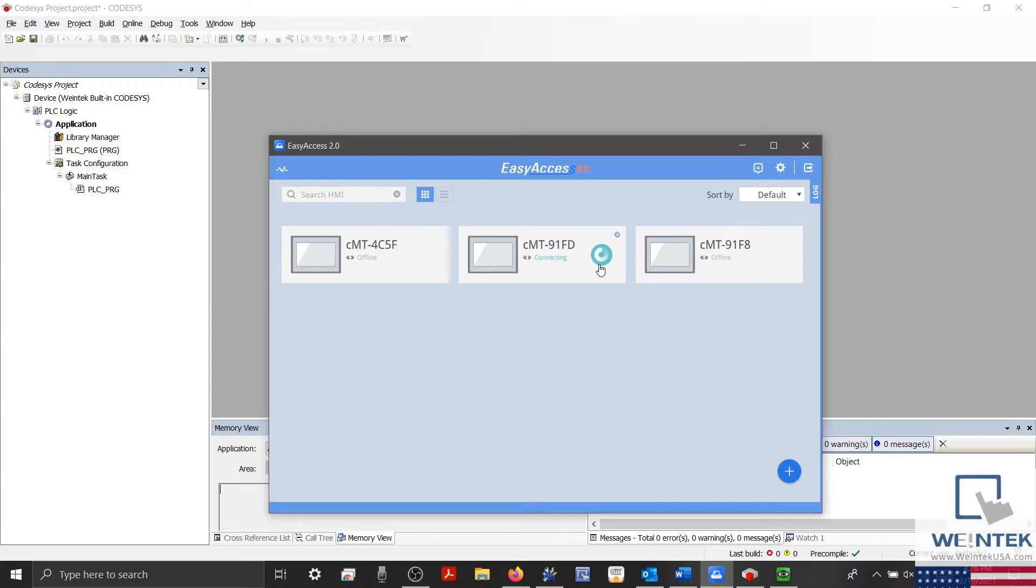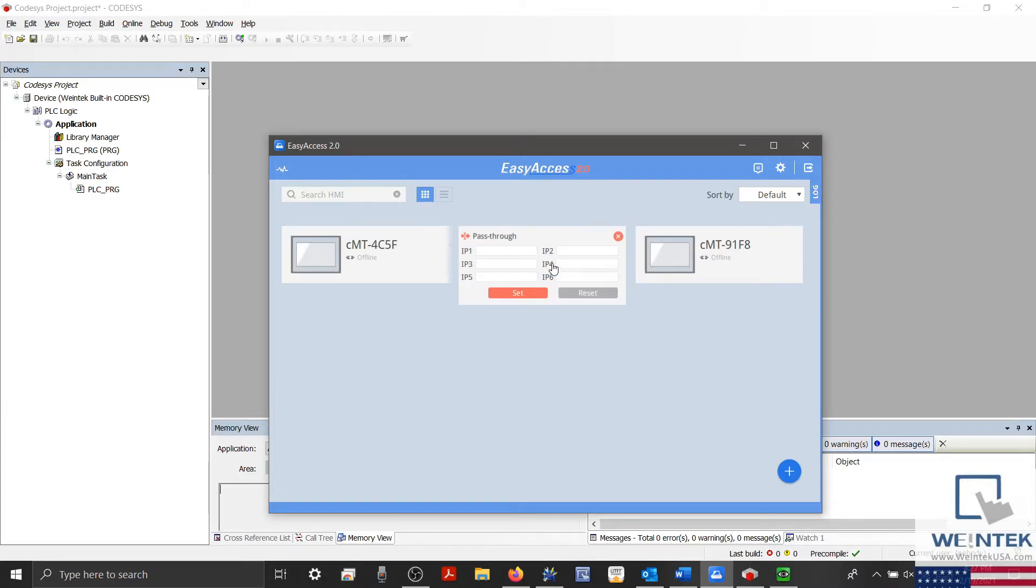Once connected, we'll select Pass-through next to the red icon, and our Pass-through menu will open. Here we'll configure the Codesys internal IP within our IP1 entry box. This is 10.255.255.2.